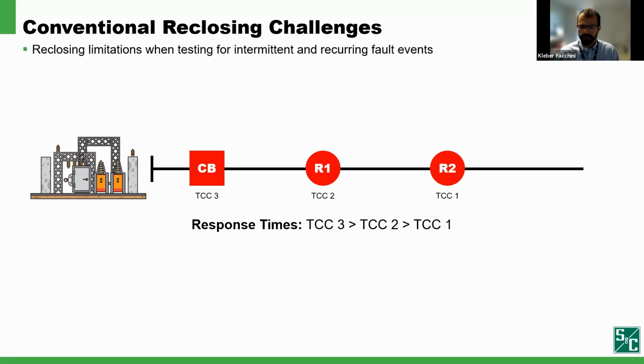A fault happens downstream of R2. R2 trips, clearing the fault, and the fault becomes highly resistive before R2 starts to test for faults and can no longer be detected. R2 recloses to test for fault presence by re-energizing the downstream feeder. Detecting no fault, R2 remains closed. The fault path eventually recarbonizes, like I explained before, producing detectable fault current. The R2 recloser trips again, reinitiating the reclosing sequence until the recloser locks out. This can happen 3-4 times depending on the set reclosing sequence. Every time the fault redevelops and a reclosing activity happens with the fault still present, full fault current levels and voltage sags are introduced in the system.